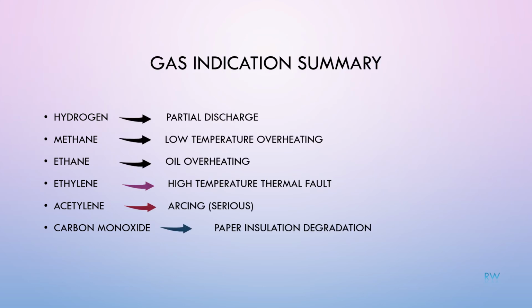Hydrogen typically indicates partial discharge, methane indicates low temperature overheating, ethane indicates overheating, ethylene indicates high temperature thermal faults, and acetylene strongly indicates arcing and is considered serious. Carbon monoxide indicates paper insulation degradation. Understanding gas behavior is critical for correct interpretation.